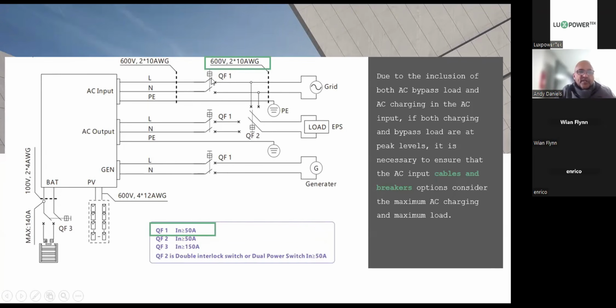Then you obviously have your circuit breaker. It goes into the input of the machine. Your output comes out, goes through a rated breaker as well, feeds the changeover, and then goes to load. And here you have your generator coming through a dedicated circuit breaker. The gen input, regardless of the size of generator that you put on the SNA 6, has a limitation of 7.2 kilowatts. In other words, it will never exceed 7.2 kilowatts input. Even if you had a 20 kilowatt generator feeding the inverter, the rated capacity here is 60 amps. It will never exceed that.